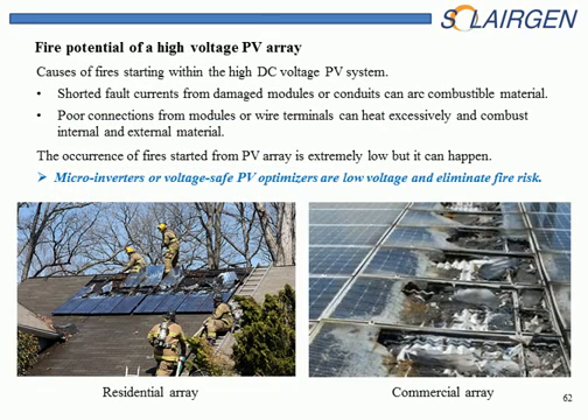In these two photos, we're looking at a residential and a commercial fire that actually occurred in the PV array itself. This could have been internal inside of a module, or it could have been on a conduit that shorted or faulted somehow. In both of these situations, the PV array was the cause of the fire. Often, if it's on the exterior of the structure, it can be seen and put out ahead of time. Now, there is a potential.